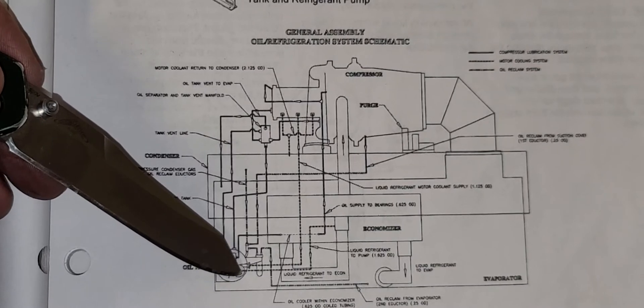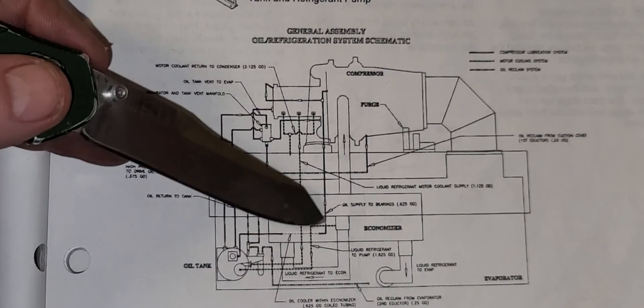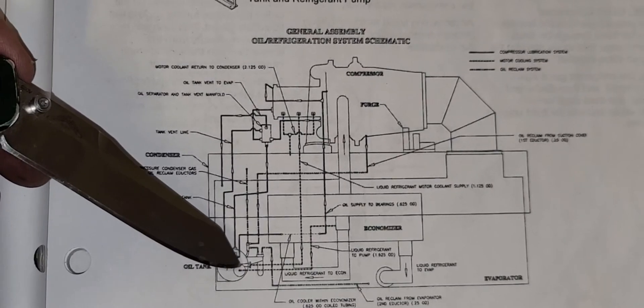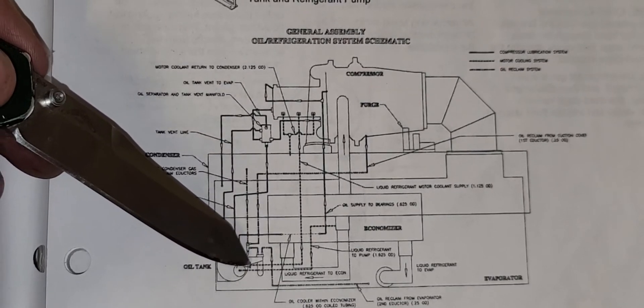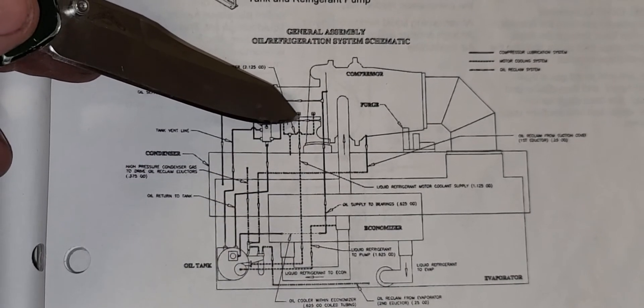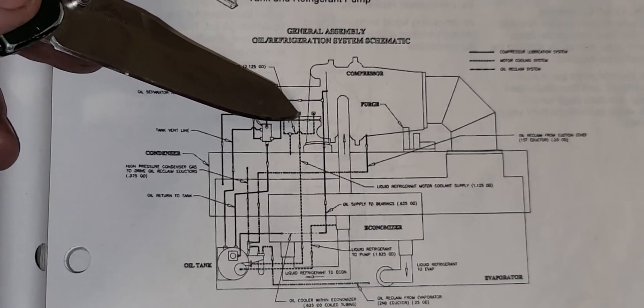So we have a pressure drop while this pump is running. That's what allows this liquid to be drawn out of the condenser. Then of course the centrifugal force does its magic and that liquid is discharged up through an orifice in the bottom of the stator on these motors.